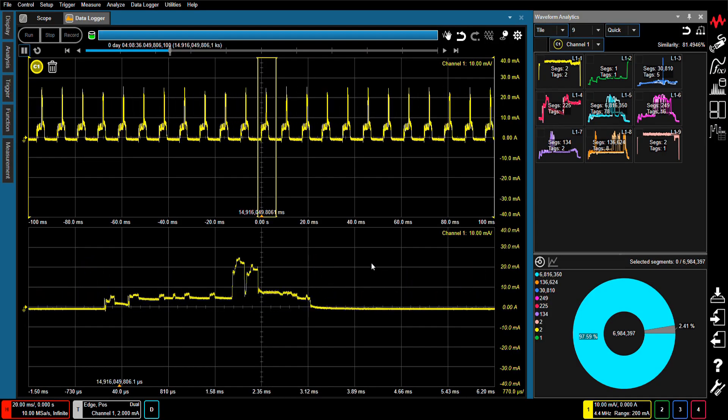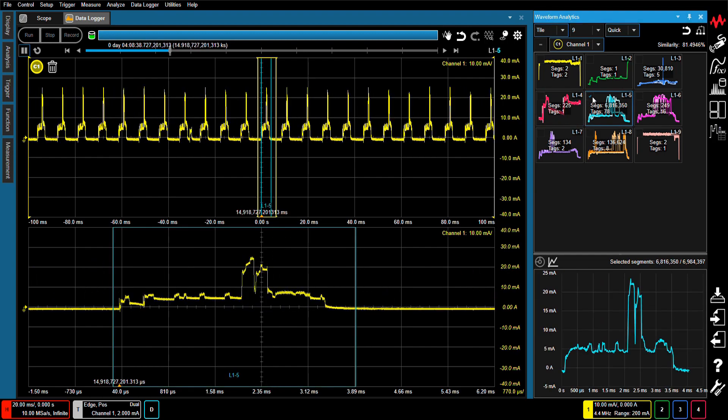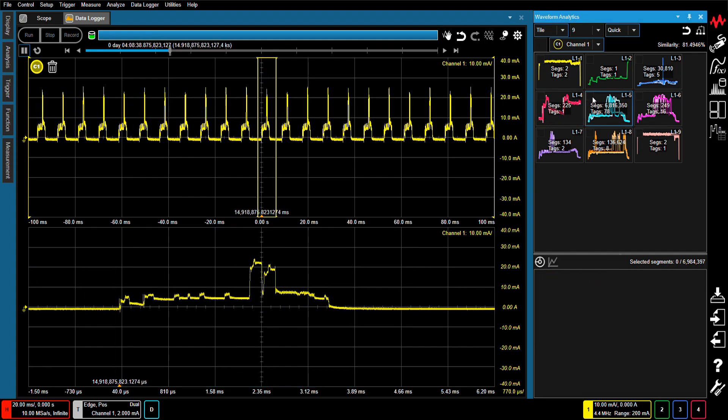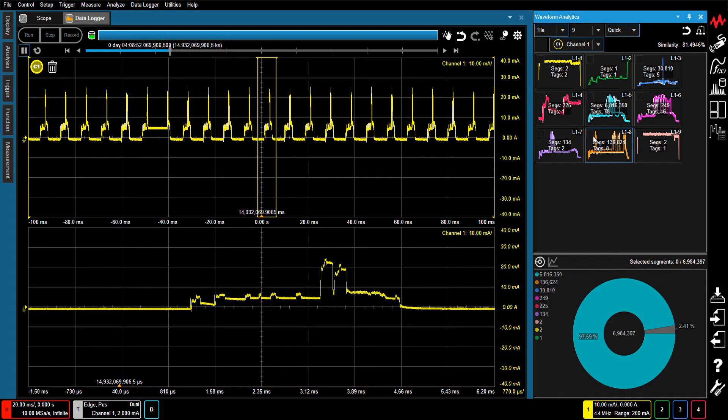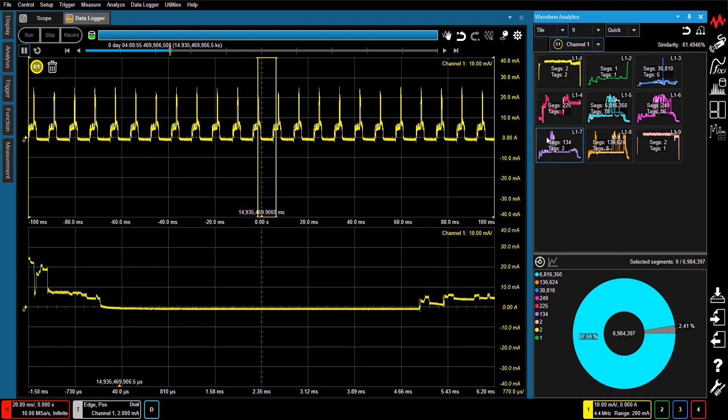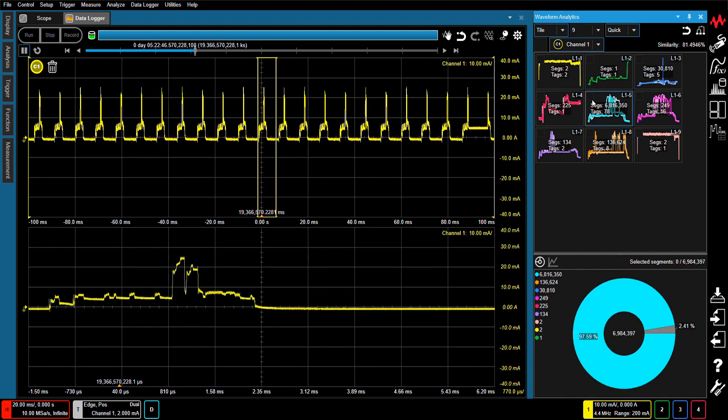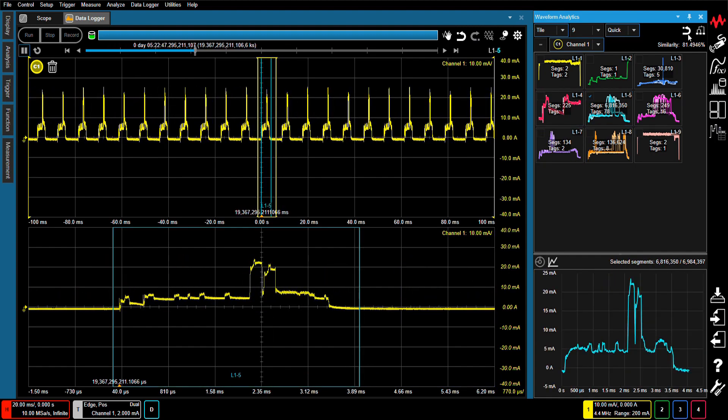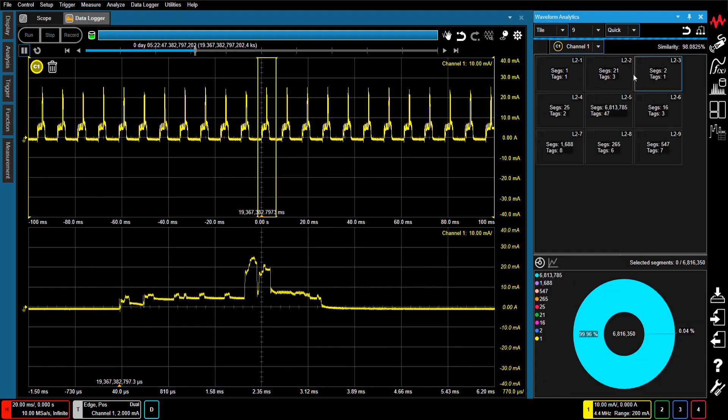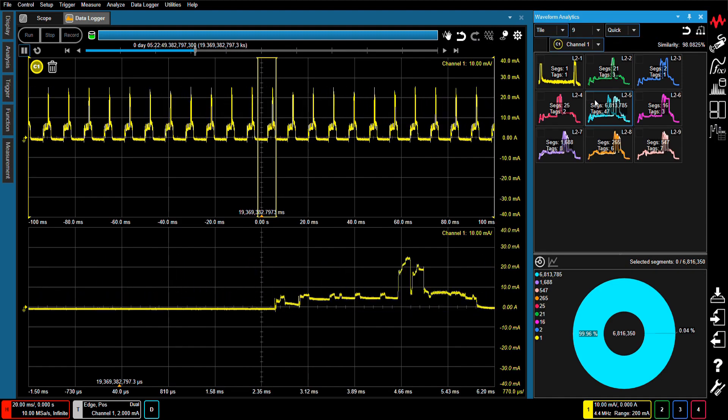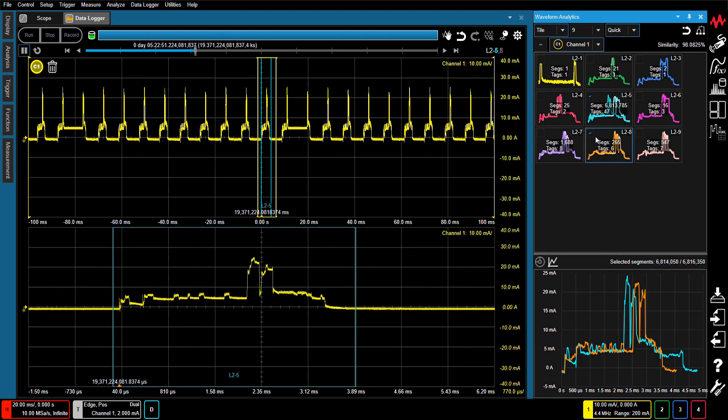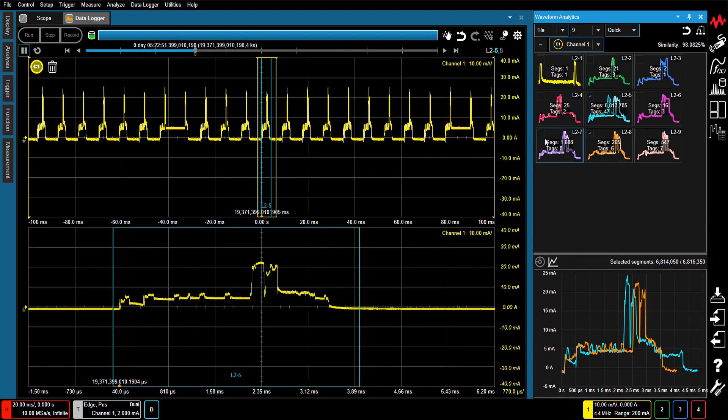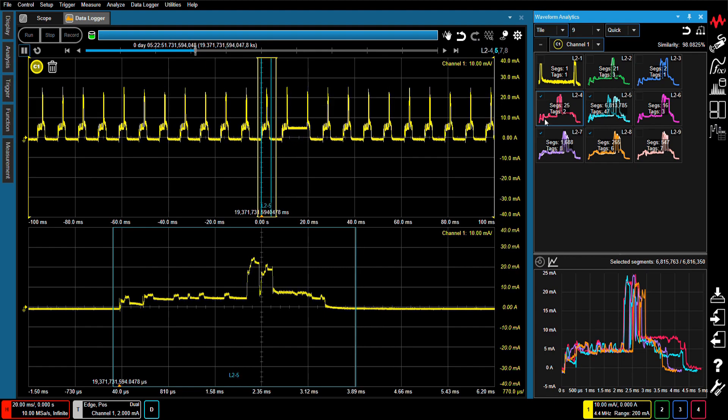Using machine learning techniques, the Anomalous Waveform Analytics feature can efficiently classify waveforms in large waveform datasets of up to 100 hours duration. Besides providing a visual display of each waveform type, the feature provides a count of that waveform's occurrences to make it easy to identify anomalies.